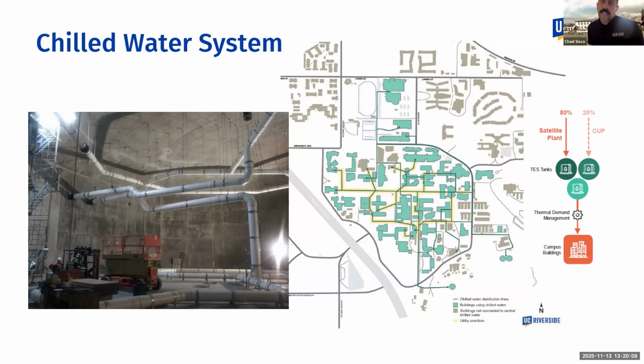Well, at the time when they built the satellite plant, they built it out for 4 chillers, but only installed 2. They installed 2 2,000-ton duplex 2-stage centrifugal chillers in a primary-secondary configuration. And with that setup, at least, UCR could produce chilled water now from 2 different plants, 2 different tanks, simultaneously or independently, whatever the load demanded. It was pretty flexible. It was a pretty nice design to add that satellite chiller plant.